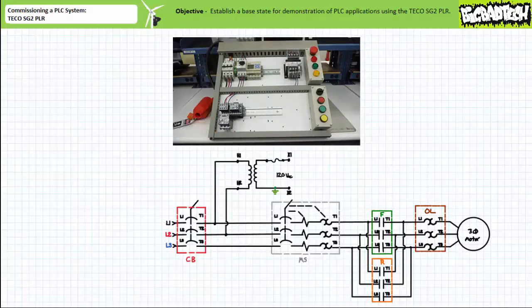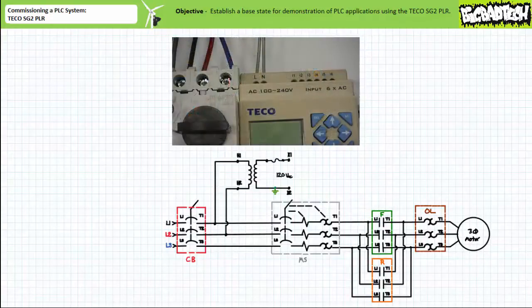Once these primary devices have been configured as illustrated, install the TECO SG2 PLR on the top DIN rail and then route the 120 volt AC control transformer high X1 and the grounded X2 output to the L and N power connections of the PLC. These connections power the internal functions of the device and are ordinarily not illustrated in the schematic.